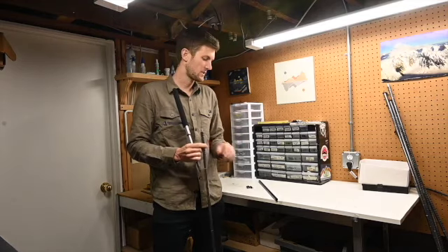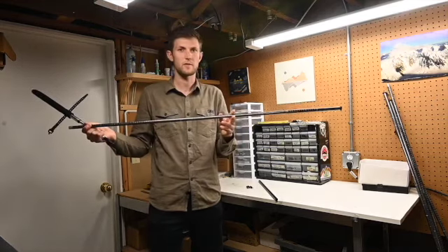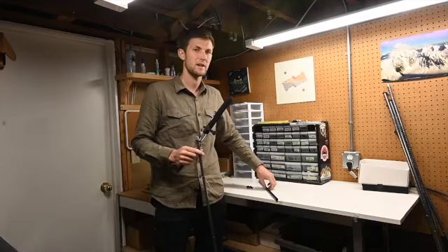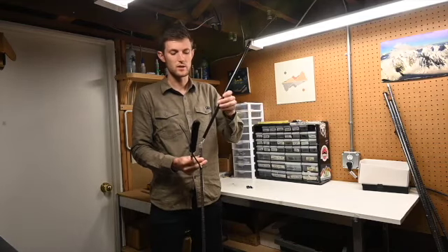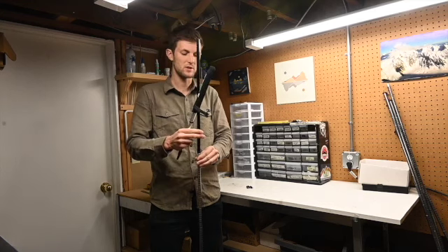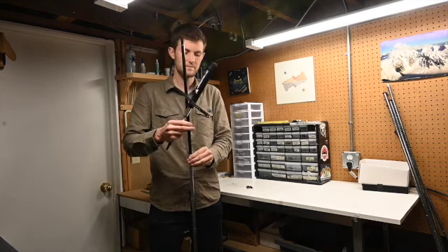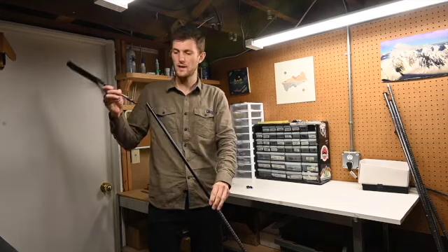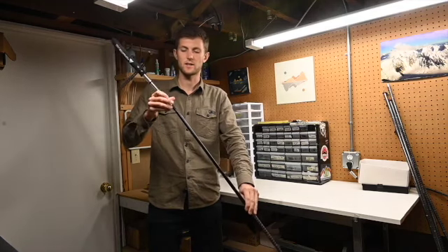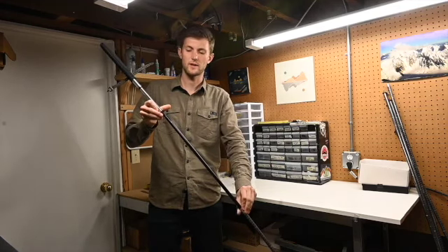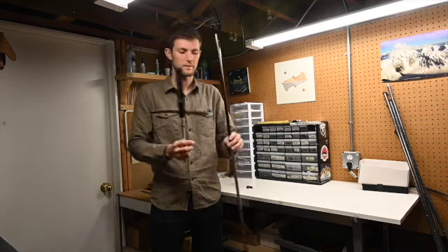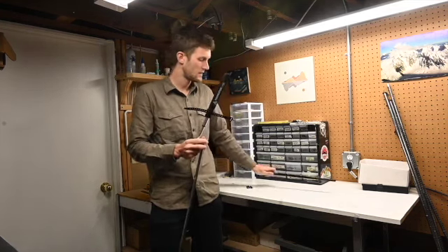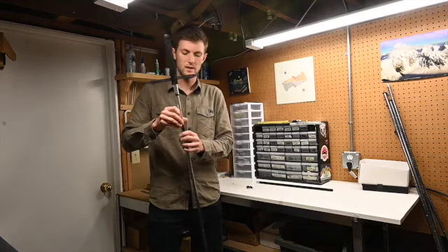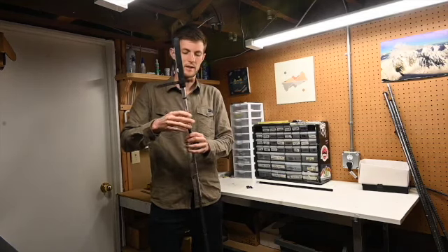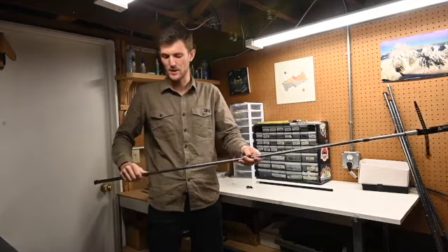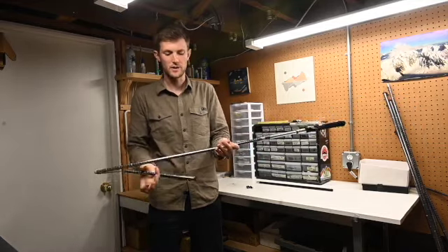If you want a little extra depth, just with the collapsible pole, you'll have about 160 centimeters. If you want to bump that to 210 centimeters, you can put your extender pole on, and this goes in between the collapsible pole and your sensor bullet. It threads into there, and then your sensor bullet threads onto the other end. I'm not going to fully thread it in right now, just for time. But most of the time, you're probably going to want to keep your sensor bullet just on the collapsible pole, just because it's easier to keep in your pack and it folds up to a nicer size.